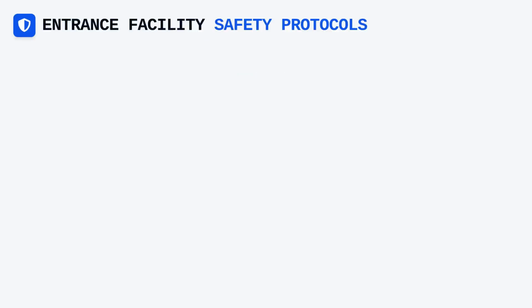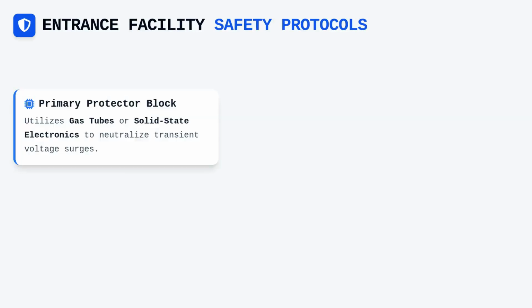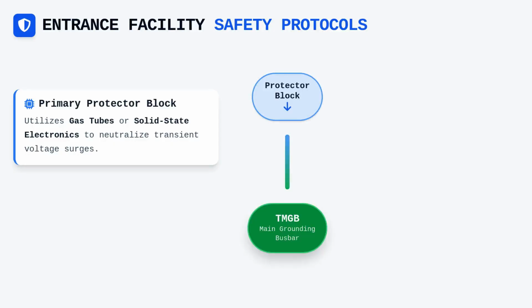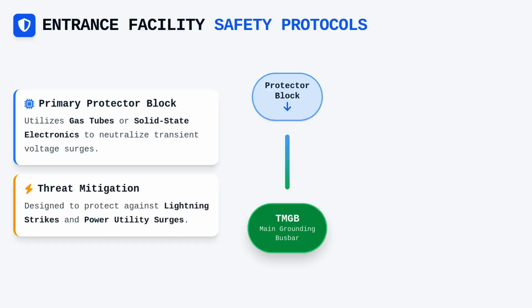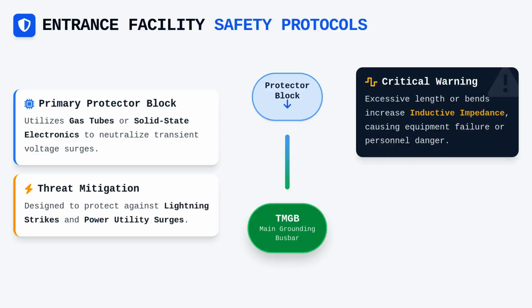Safety protocols mandate the inclusion of a primary protector block that contains voltage surge suppression devices, typically utilizing gas tubes or solid-state electronics to handle transient surges. These protector devices must have an ultra-short, low-impedance connection to the telecommunications main grounding busbar, or TMGB, to be truly effective during a lightning strike or an external power utility surge.